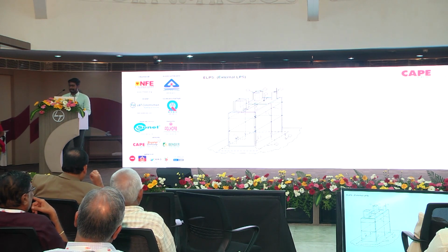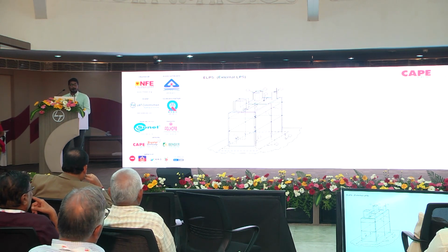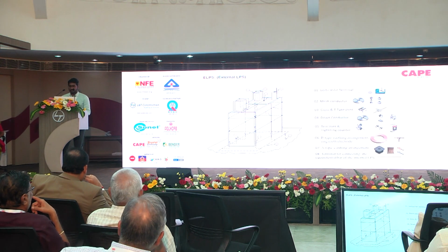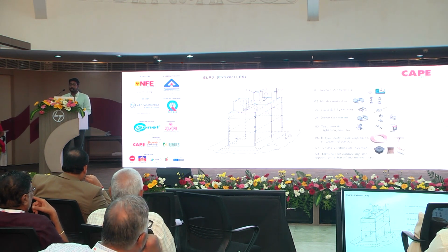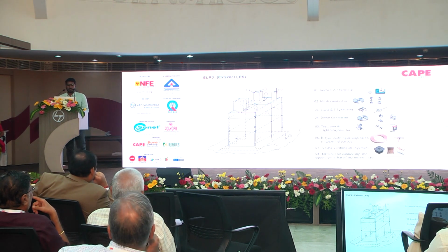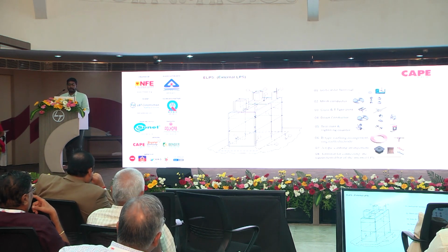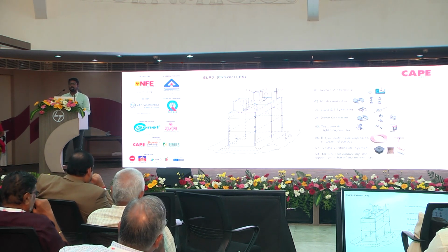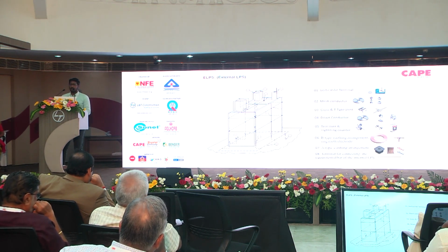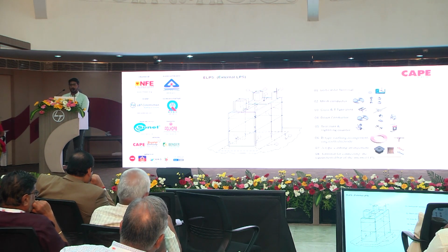Now, in external lightning protection, just to give an overview with a pictorial representation. So this is a building. This is the first parameter which I want to explain, the air termination part. In air termination, at the terrace level, we'll start with the vertical air terminal, because in air termination, as we saw in the previous session, there are totally 3 methods. One is rolling sphere, which is used to identify the probability of a lightning strike happening in the building, second is protection angle, and third is mesh method.